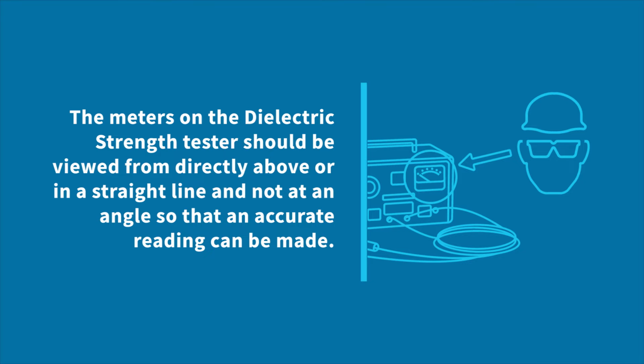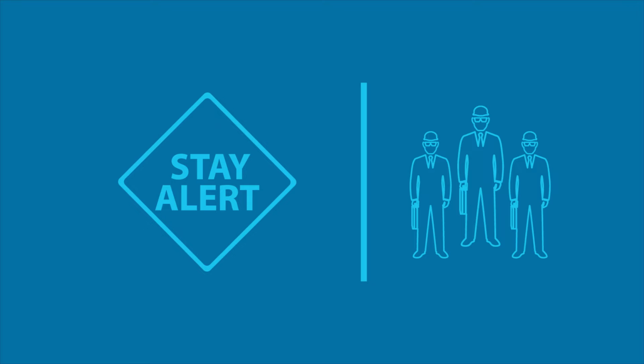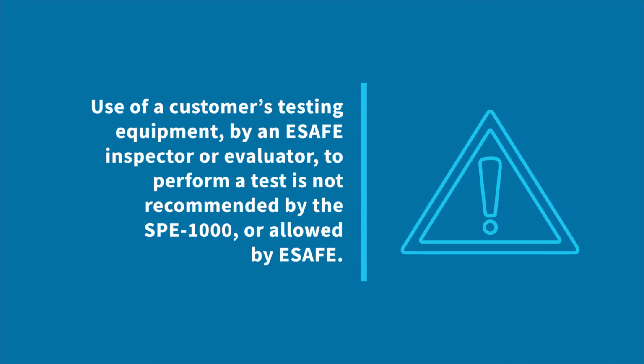It is the inspector or evaluator's responsibility to ensure that the test apparatus is appropriately calibrated and for verifying that the measurement apparatus, including interconnecting cables, is in good working condition before performing the tests. The use of a customer's testing equipment by an ESAFE inspector or evaluator to perform a test is not recommended by SPE 1000 or allowed by ESAFE.